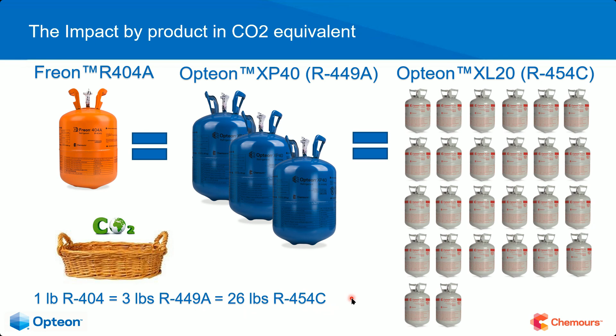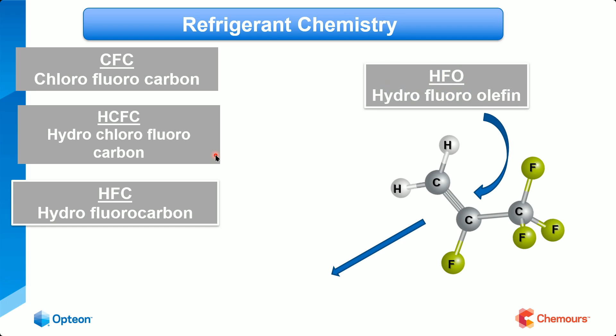So what's an HFO? Let's talk about that - let's go through some refrigerant chemistry. Now, I'm not a chemist, but I understand this. We had CFCs under the Montreal Protocol - that would be like R12, chlorofluorocarbons. Then HCFCs, hydrochlorofluorocarbons, with less ozone depletion - this would be like good old R22. Then they started to notice the hole in the ozone, took precautions, and connected it to the C at the beginning, which stands for chlorine. So they removed that and we went to HFCs, hydrofluorocarbons, which don't cause ozone depletion because there's no C at the beginning. Now we're moving from HFCs, because of the GWP or global warming potential, to HFOs. And a simple analogy for an HFO is that it's really an HFC in disguise.